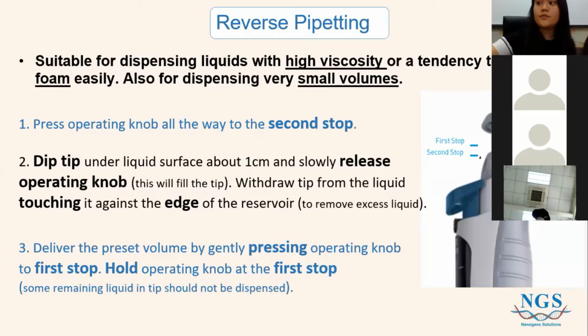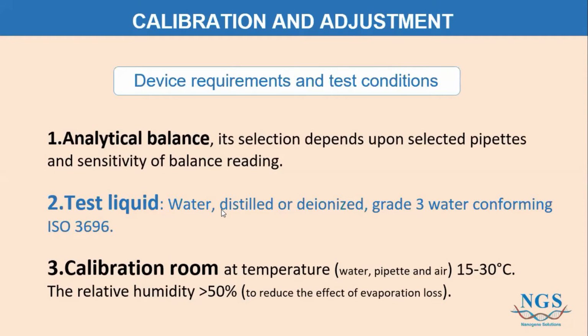All right, so this would conclude the pipetting techniques. So we've learned 2 techniques today, and then I will continue with how to calibrate your pipette. All right, so before you calibrate your pipette, you need to know where your pipette is at. Is it good? Is it working the way it should? So there's a way to test that. So before you test, you will need a few devices and some conditions. So first thing you'll need is an analytical balance, a digital analytical balance. Test liquid, you can choose distilled water, and a calibration room that is at room temperature and has the appropriate humidity. I would say above 50%. That would be useful if you want to reduce any evaporation during your reading.